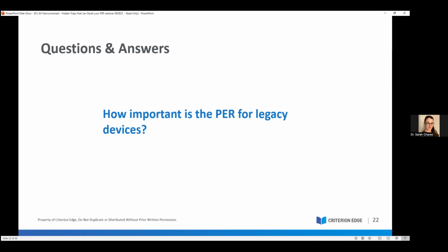That's what you need to know. And that's where that state-of-the-art search really helps you determine the strategy, and then also helps you determine if there may be any limits, based on changes that are necessary to your intended purpose, to still be considered state-of-the-art. You may have to limit your intended purpose in order to go in as sort of a legacy device.